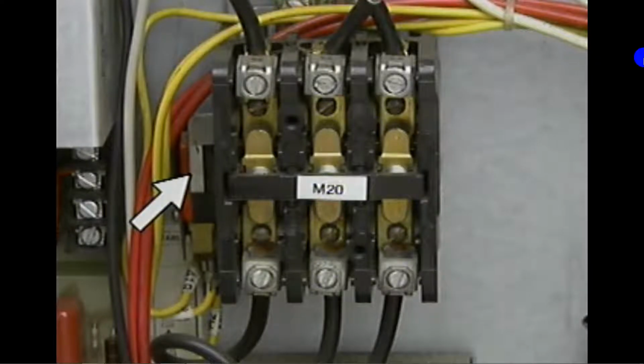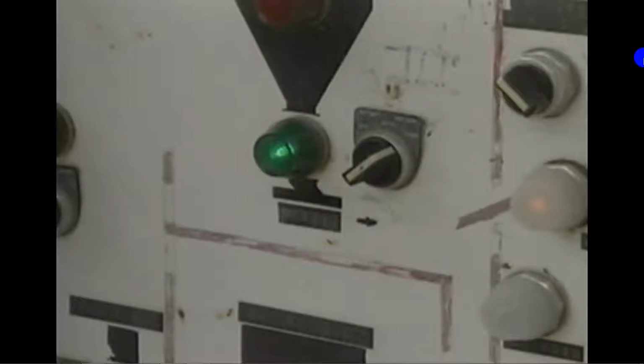Auxiliary contacts are usually attached to the armature and operated by it. These contacts are used to perform auxiliary control functions, such as providing current for indicating lights like the ones used to indicate whether a motor is on or off. An advantage of a magnetic contactor is that it can be energized from a remote location using a voltage that is lower than the motor's operating voltage. This way, personnel are not exposed to high voltage when they start and stop high voltage motors.